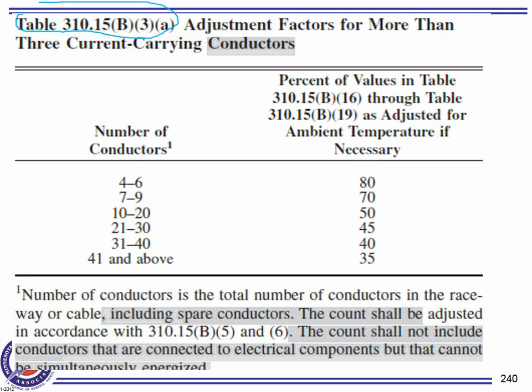All right, number of conductors. If your conductors are 4 to 6, you have to derate them by 80%. So it's really easy. What happens if you have 50 conductors in the same conduit? Look what happened. You get 35 cents on every dollar that you put there. To give you an idea, who in his right mind would do something like that? So if your conductor is 100 amps, you can only use 35 amps out of it. That's crazy, isn't it?